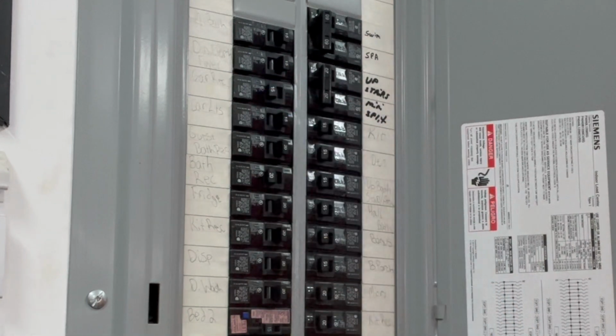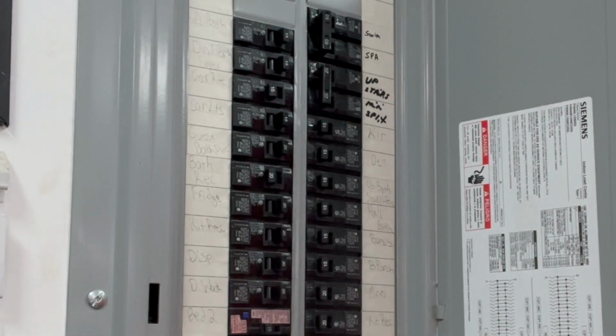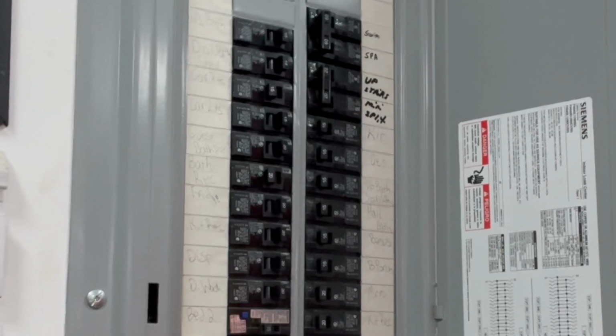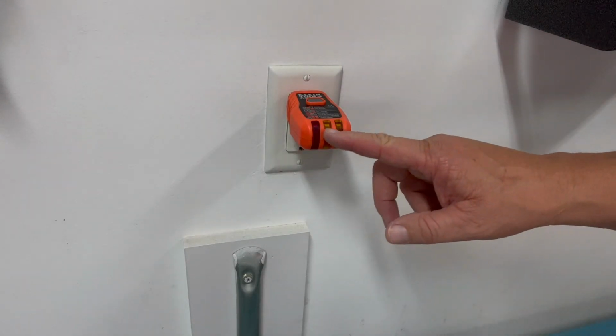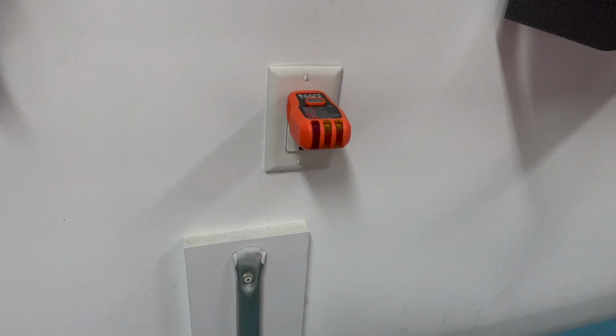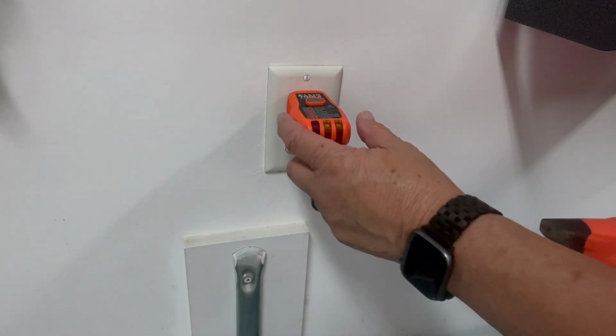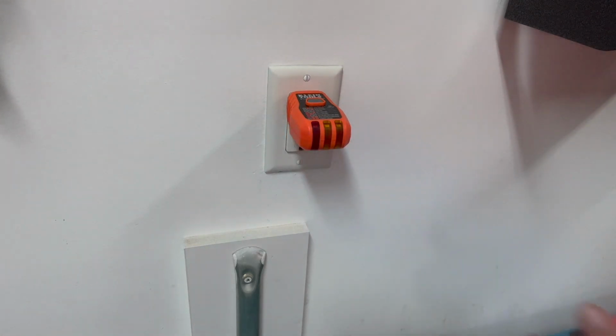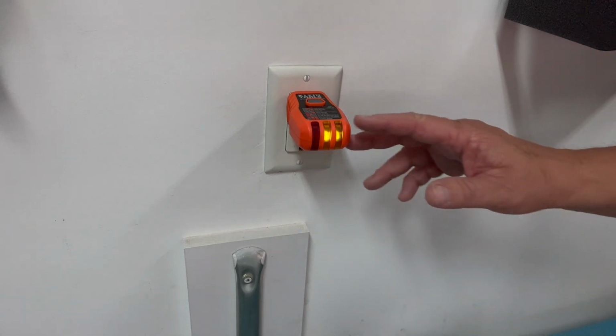We'll turn it off. We'll go back to the electrical outlet and see if it's tripped. So as you can see, the yellow lights are off. That would indicate that is the correct circuit. Now before you work on it, you don't want to use this to verify that the circuit is not hot. You want to use another electrical tester to double check that. We'll turn the breaker back on. Okay, we've got the circuit turned back on.